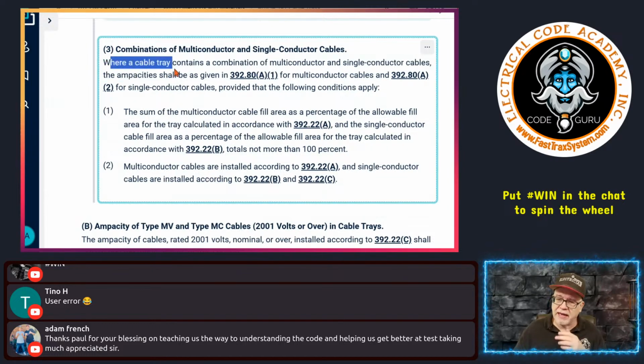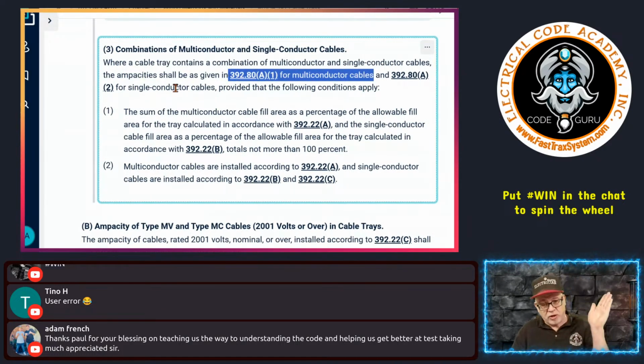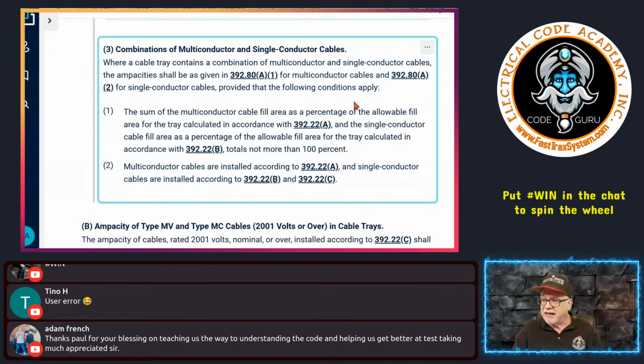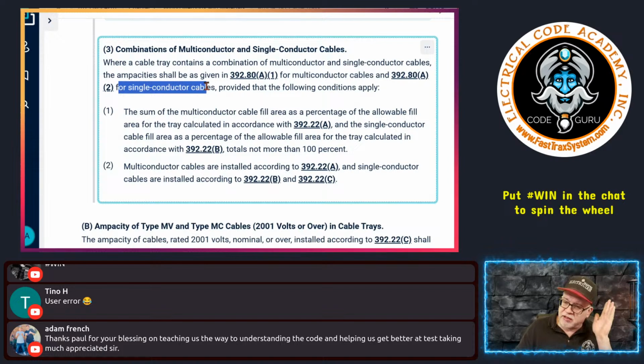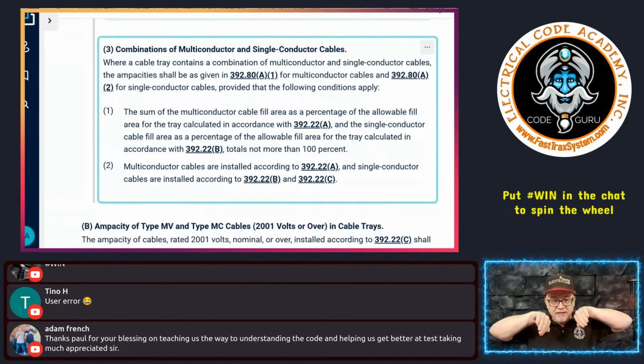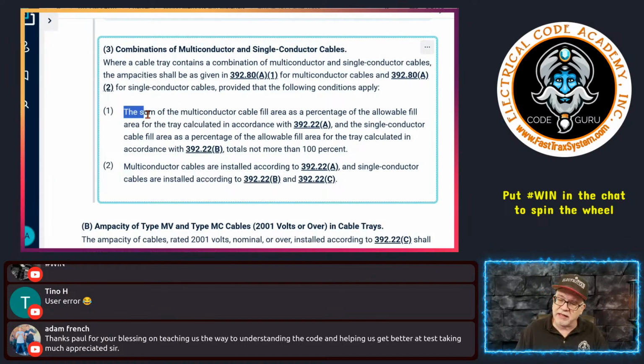It says, where a cable tray contains a combination of multi-conductor and single conductor cables, the ampacity shall be given in 392.80(A)(1) for the multi-conductor cables. So that's the ampacity for those. So do like we just did today. And then it says, use 392.80(A)(2) for those single conductor cables, okay? And you can do them separately. They can be in the same tray, provided you have these following conditions.